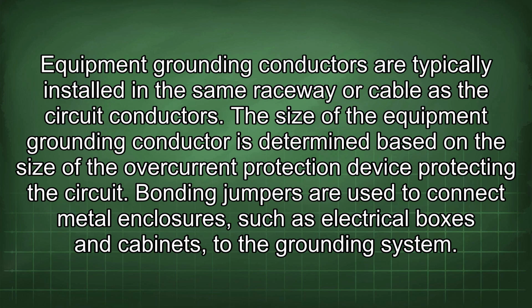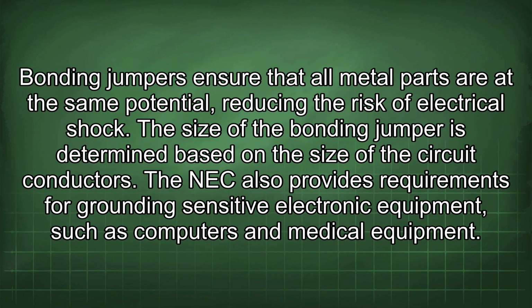The size of the equipment grounding conductor is determined based on the size of the overcurrent protection device protecting the circuit. Bonding jumpers are used to connect metal enclosures, such as electrical boxes and cabinets, to the grounding system. Bonding jumpers ensure that all metal parts are at the same potential, reducing the risk of electrical shock. The size of the bonding jumper is determined based on the size of the circuit conductors.